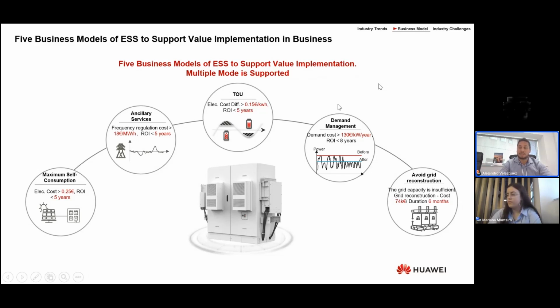Demand management, which can be seen here in the form of peak shaving. So you have a high peak in demand and you want to use energy from your battery because there is a charge for power. With a demand cost of 130 euros per kilowatt per year, this return of investment can be done in under 8 years.